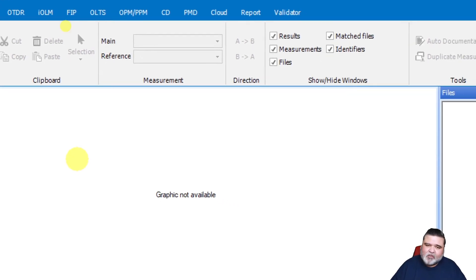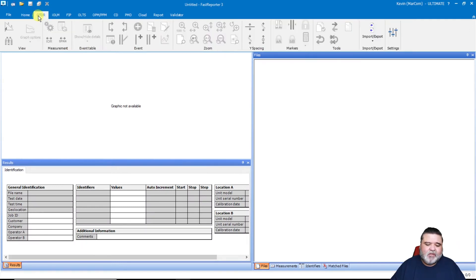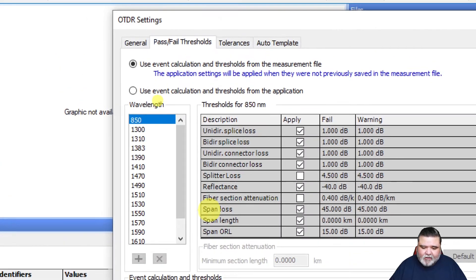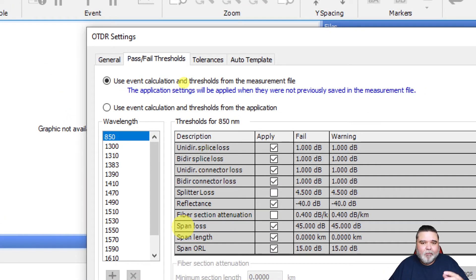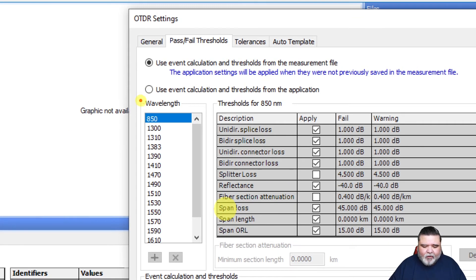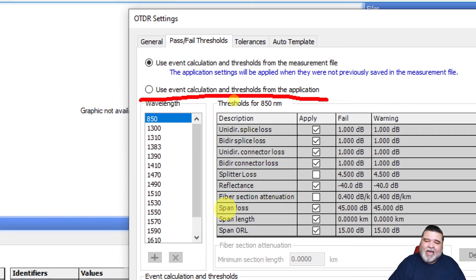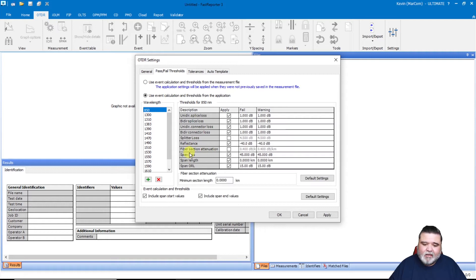Now I'll set the individual parameters for the different test types. For this demo I'm just going to do bi-directional OTDR, so I'll select OTDR. All these grayed-out icons will light up when you have an actual OTDR trace loaded and selected. I'll go all the way over to settings. Under settings I have two options: use event calculation and thresholds from the measurement file, meaning Fast Reporter analyzes data based on thresholds set in the test set — I don't want that because it's fairly inconsistent. I'm going to use event calculations and thresholds from the application — Fast Reporter 3.